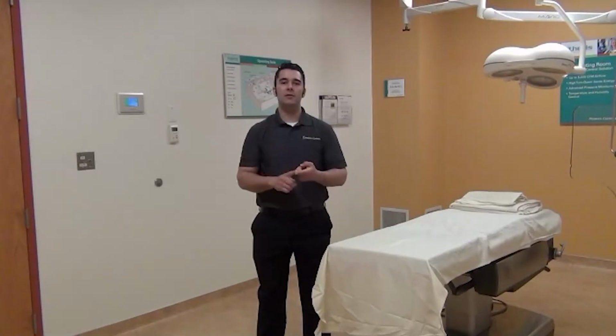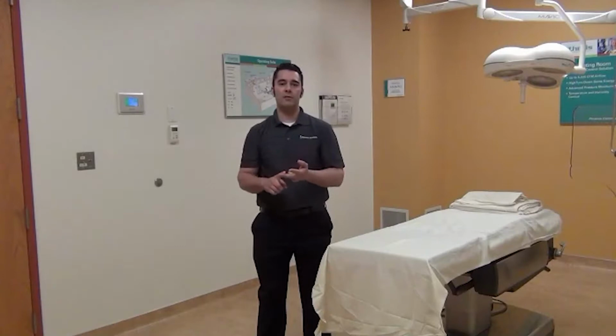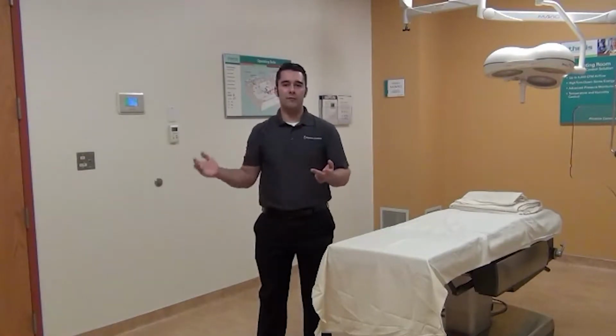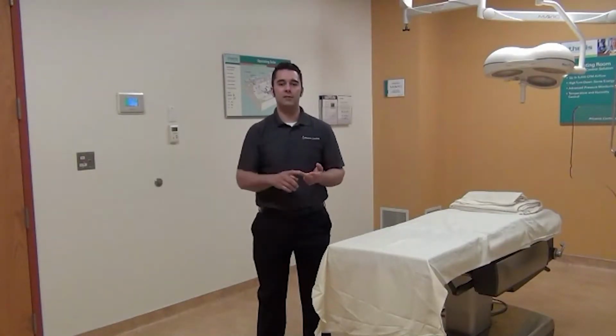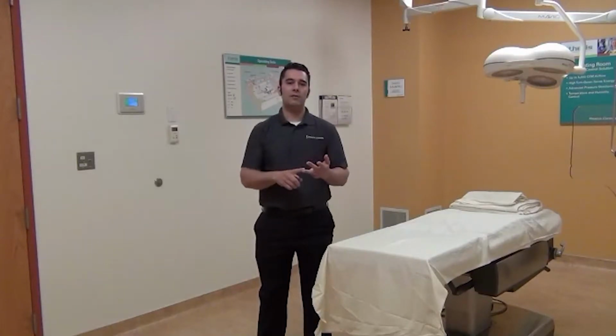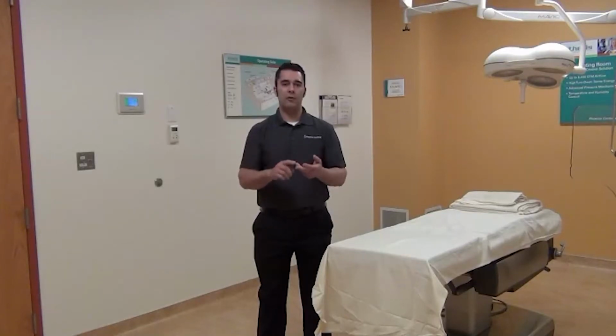As I hope you can see from the video, the Phoenix Controls products provide the turn down that is necessary to maintain occupied and unoccupied flows in the space. They also will guarantee that the pressurization remains constant across the door, so that even transitioning from occupied to unoccupied modes, I will never have reversion or the pressure flipping inside of the space. And I can also guarantee that they'll get there relatively quickly, so they're stable once they get to their set point. They're going to hold the pressurization more accurately. You don't have maintenance inside of this space. So Phoenix Controls products are always the best choice for healthcare.